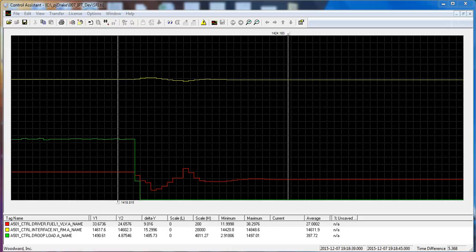Hello, my name is Gary Owens, and for our senior design project, we designed a new gas turbine fuel control and protection system. One of the major performance enhancements we were trying to achieve was a better load rejection response. The existing customer system often did not stay running when major load swings above 1 megawatt occurred on the system, either flaming out the engine if the fuel cut back too much or overspeeding the engine if it didn't cut back fast enough.